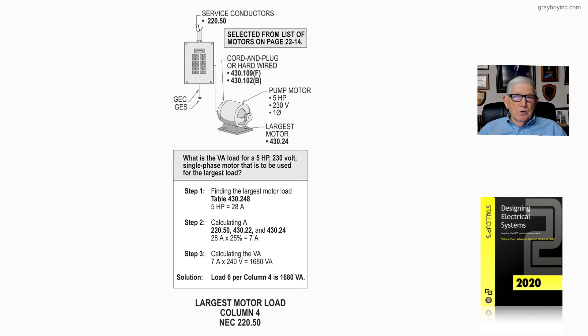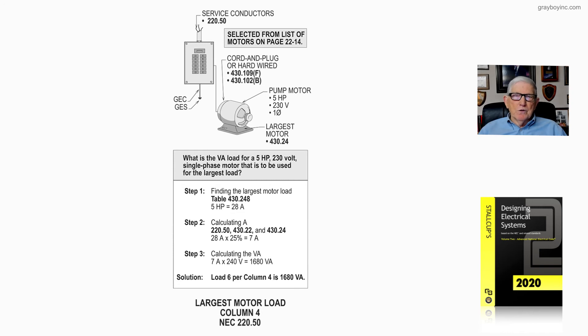Note: 220.50 as well as 220.14C — motors are so important that you have to get out of Article 220 to do your calculation, meaning to select your percentages to use. That's 430.22 for a single motor, and 430.24 for two or more motors, or two or more motors with other loads.